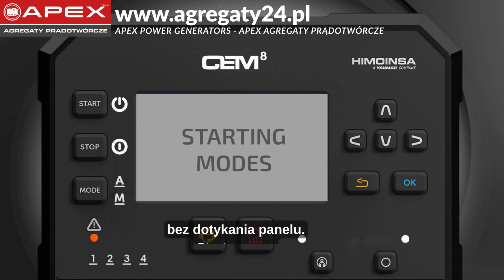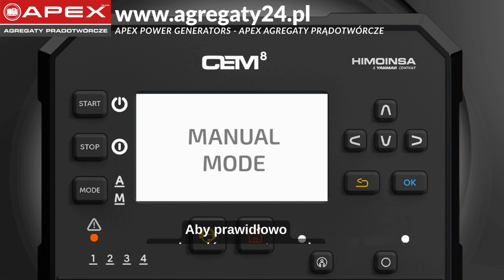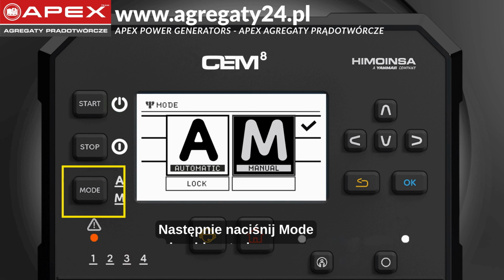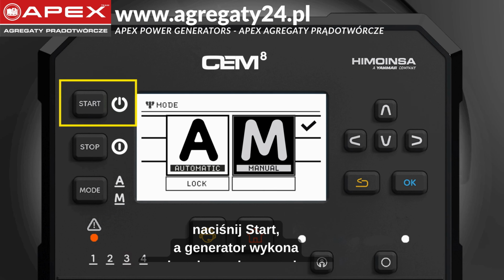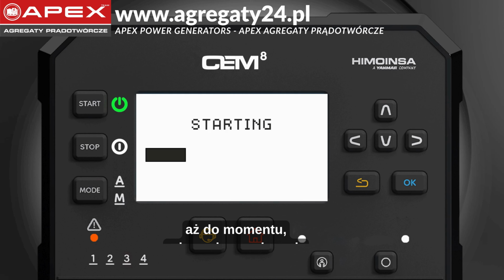Manual start. For a correct manual start, first make sure the area is clear, well ventilated, and free of people, obstacles, or materials that could pose a risk. Then press mode and select manual. If the unit is in auto, a manual start will not be possible. Once in manual, press start and the generator will execute its start sequence until you command a stop with stop.